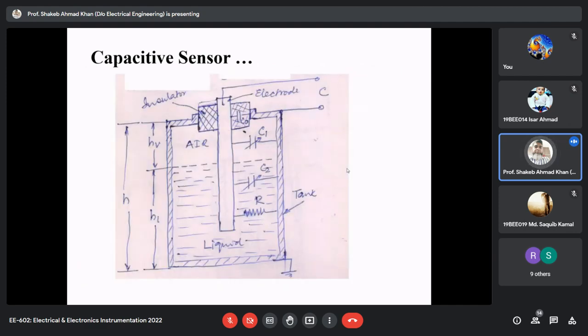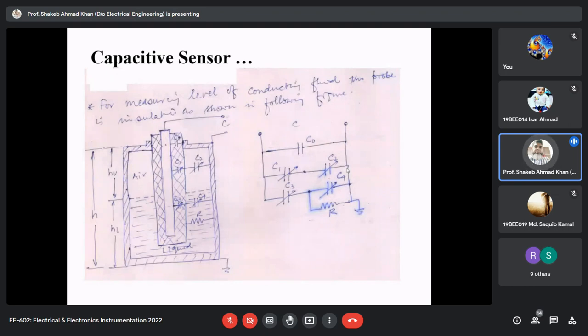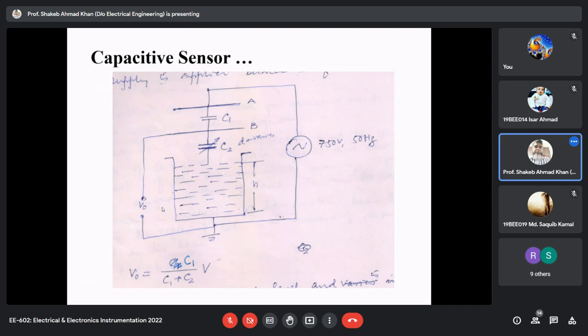Now if we want to measure the liquid level for a conducting fluid with this setup, one suggestion is that we should insulate the inner electrode, and then the equivalent circuit will be something like this. In this case too, although things are a bit complex, the equivalent capacitance will vary as the liquid level varies, and by measuring the capacitance we can measure the liquid level. So this is the setup option for conducting fluid.